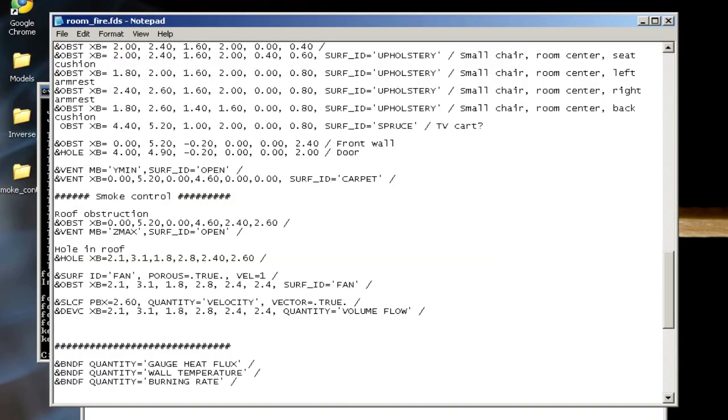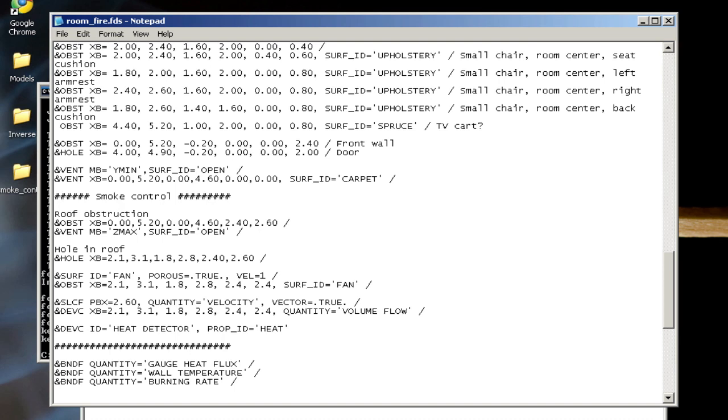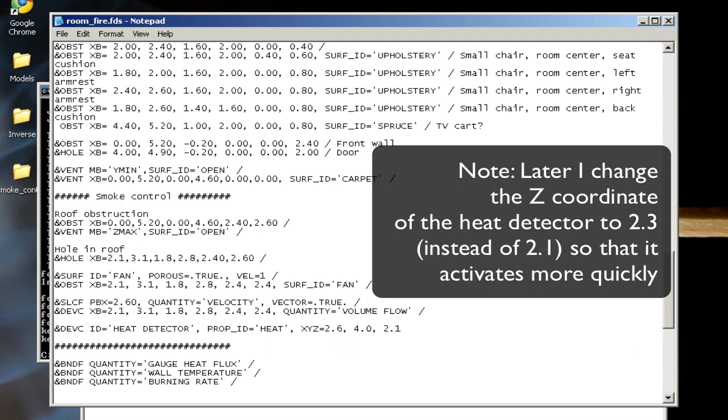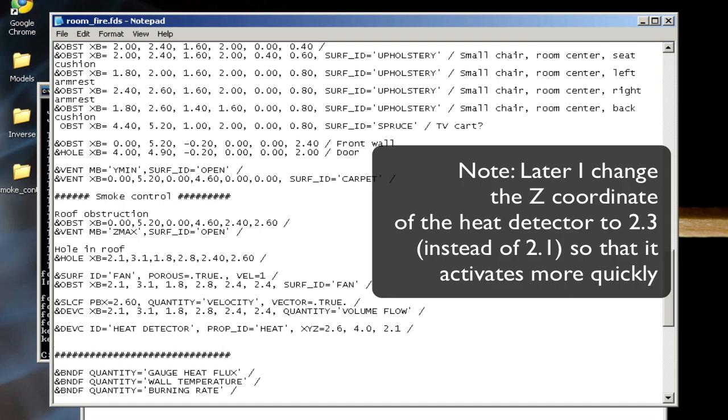I want to add in a device ID—I'll call it heat detector. I'll set the property ID to heat and set the XYZ location. I want to set this so that it's over the fire on the couch so it warms up really quick, just for demonstration purposes. So 2.6, 4.0 is near that back wall, and 2.1 is just below the ceiling.